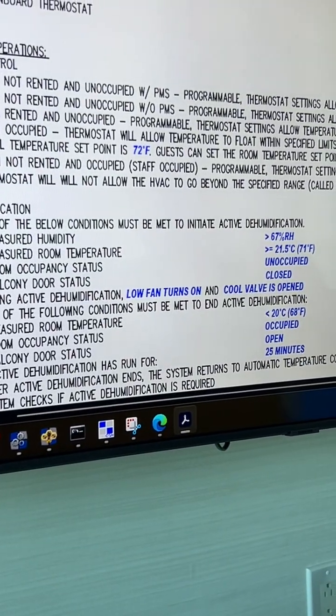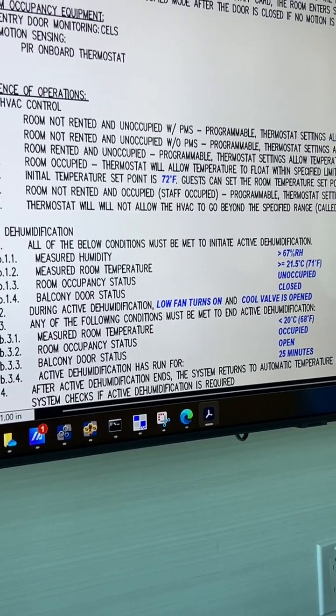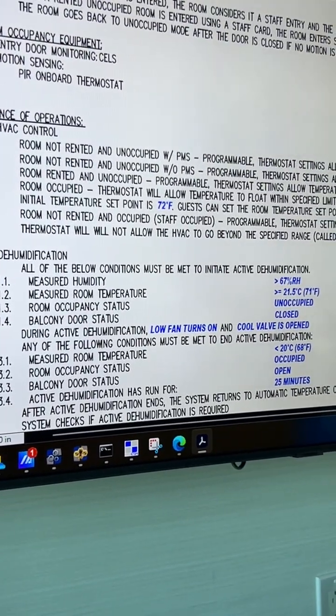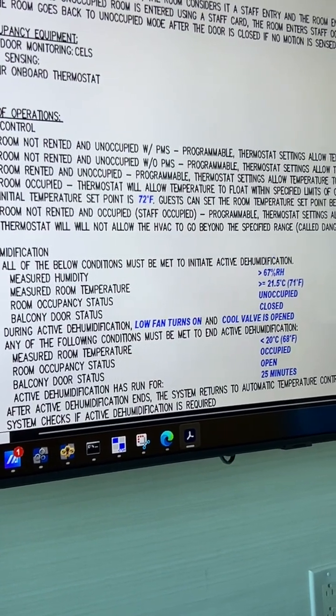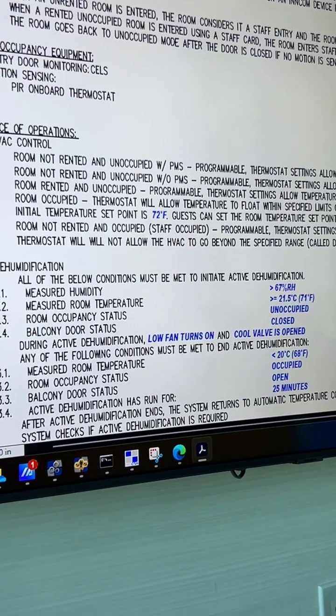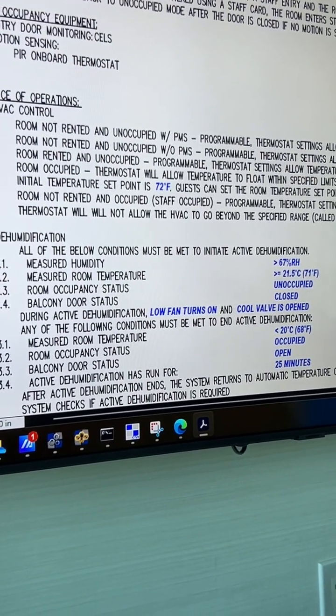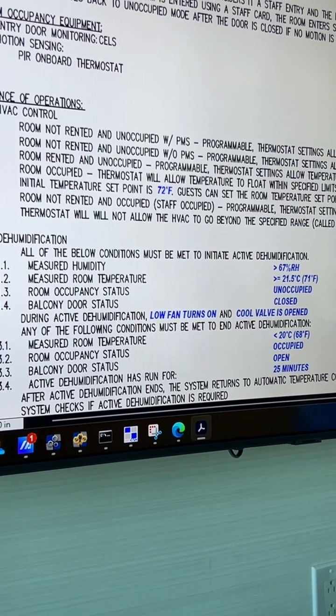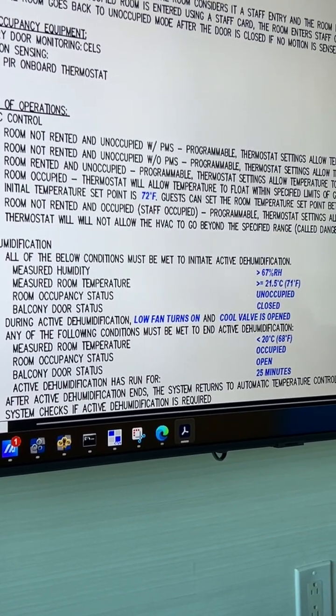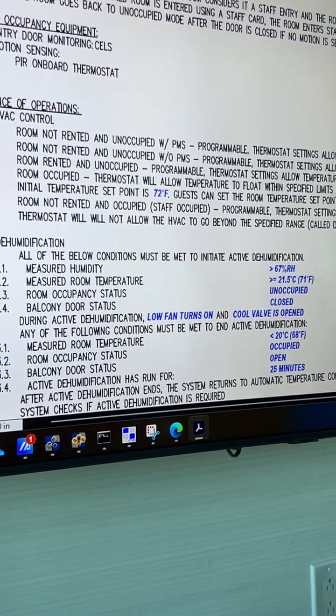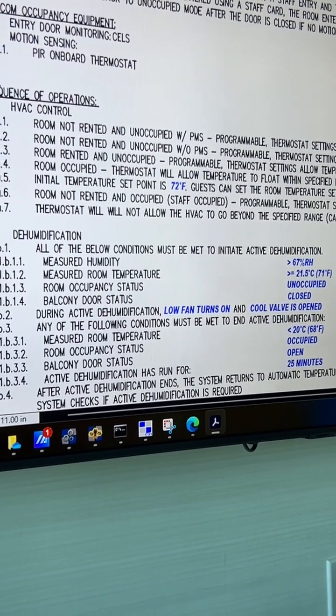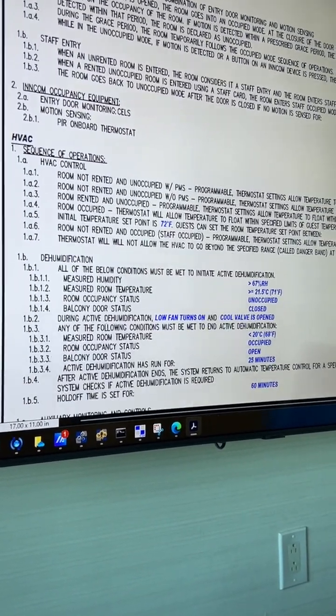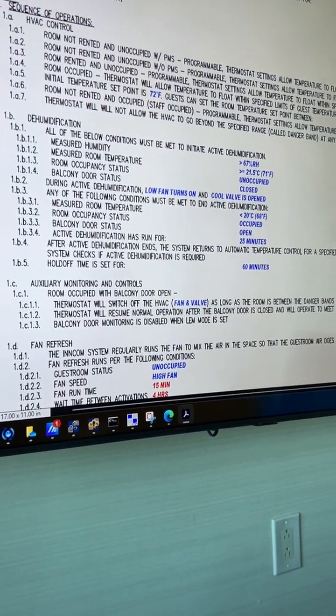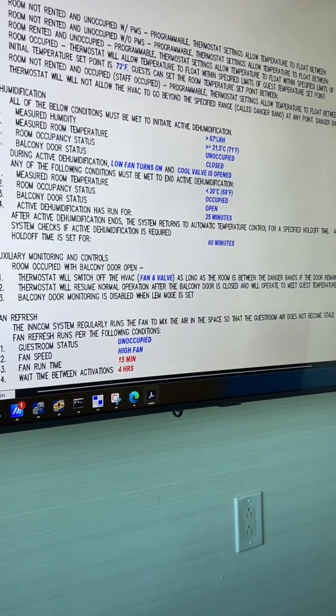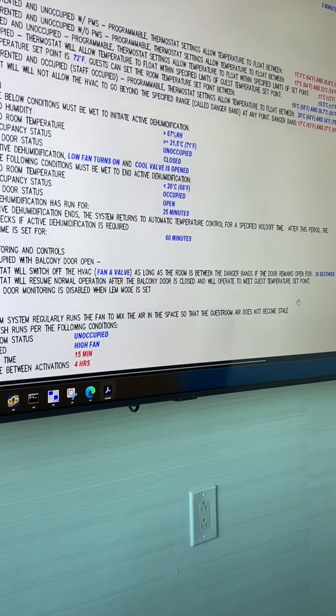Second. Here are your dehumidification settings. So if the room is above 67% humidity, and the room temperature is above 71 degrees, and the room is unoccupied, and the balcony door is closed, it will turn on low fan and cooling for 25 minutes, unless the room gets below 68 degrees, becomes occupied, or the balcony door opens. Okay. So that's just what this is saying. Got it. Balcony door opens, everything turns off after it being open for longer than 30 seconds.